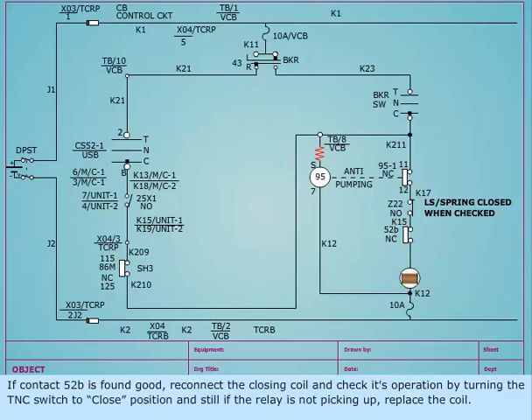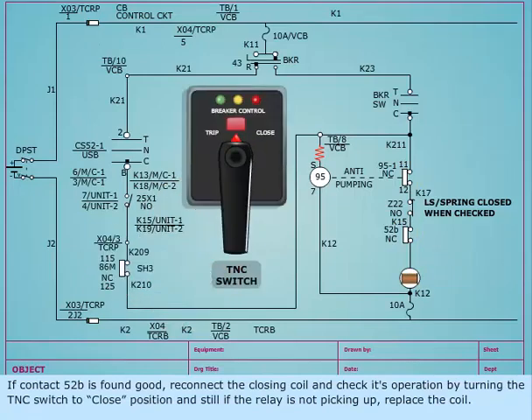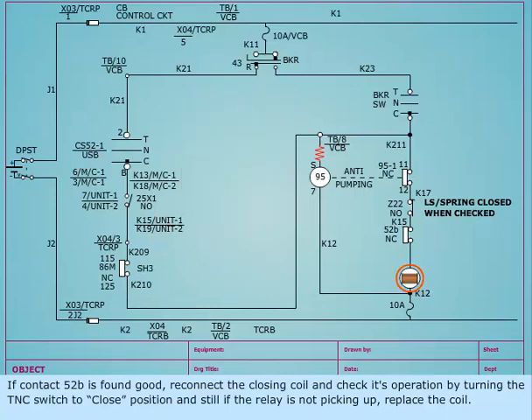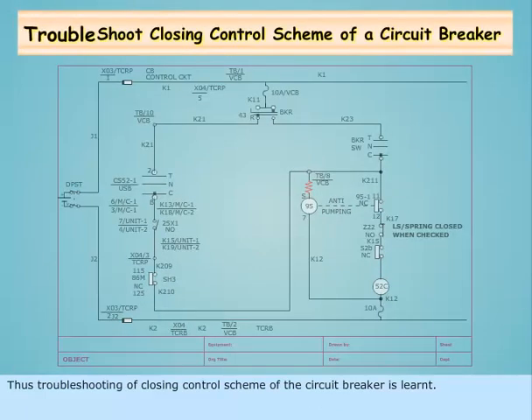reconnect the closing coil and check its operation by turning the TNC switch to close position. If the relay is still not picking up, replace the coil. Thus, troubleshooting of the closing control scheme of the circuit breaker is learned.